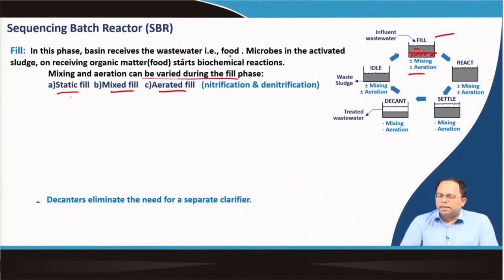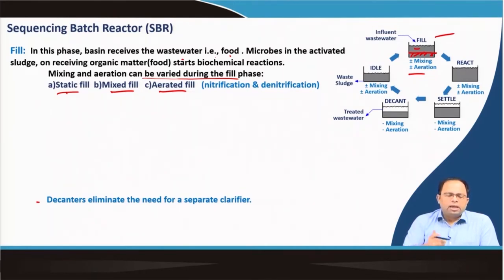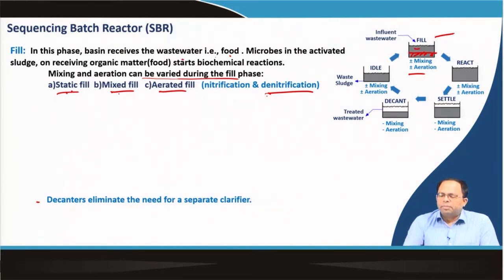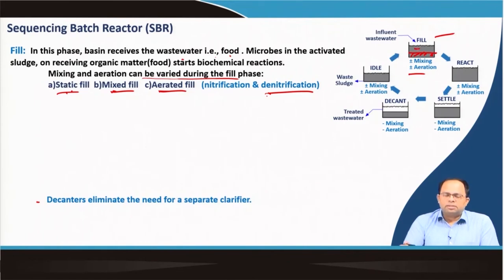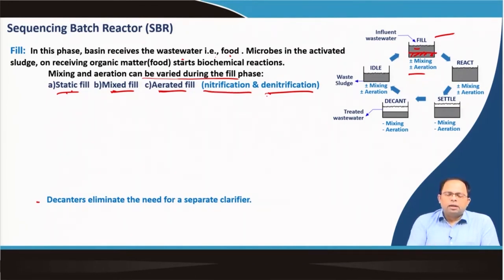In the static fill process, neither mixing nor aeration takes place, so anoxic conditions prevail — no oxygen — and that is when denitrification occurs. In mix fill, mixing happens but aeration does not, so some anoxic condition exists and denitrification also occurs. In aerated fill, the aeration process starts as well, leading to activity by aerobic bacteria, and nitrification can also happen. So in SBR we can achieve both nitrification and denitrification along with normal decomposition of organic content.